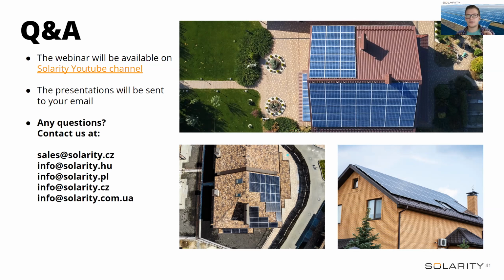But during a power outage in the daytime, when the sun is still shining, you won't have the possibility of backup supply directly from the panels in a retrofit setup. With the Solax solution, during a power outage, supply first comes from the PV installation, and then, to cover your demand and loads, from the battery system. But in the case of retrofit, supply will come just from the energy storage system.